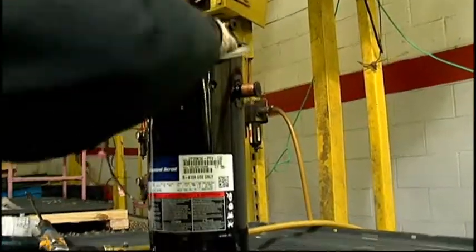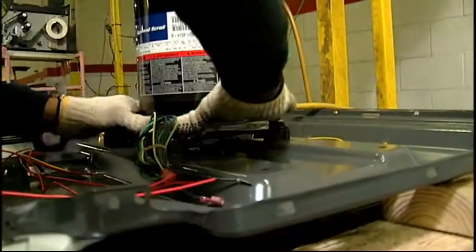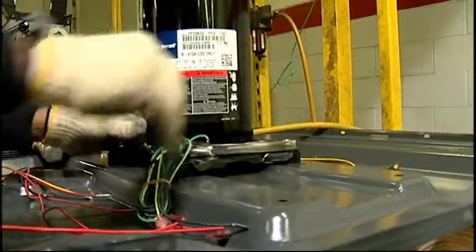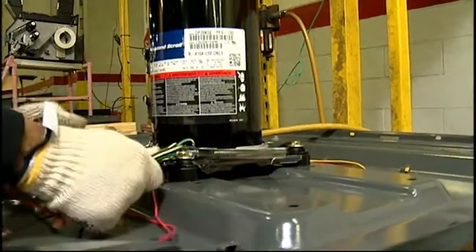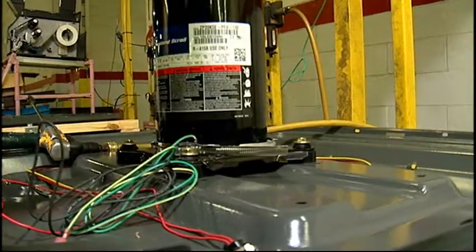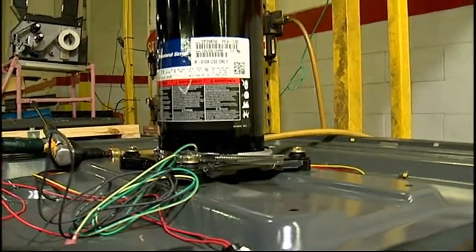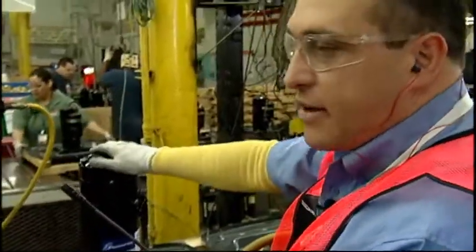We also went in and put a heater band. If you look in here, you will see the heater band. The whole purpose of the heater band on the compressor is to make sure we don't have any liquid going into the compressor, because that will create slugging and kill the compressor.